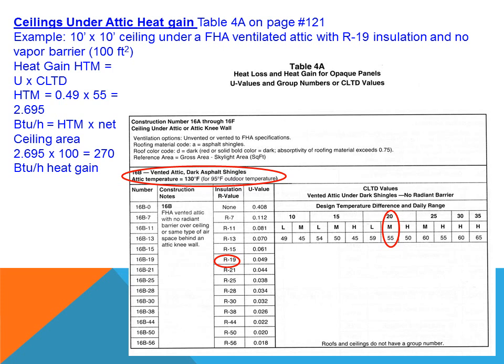Another heat gain we need to consider is the heat picked up through ceilings, because ceilings above an attic can gain a great deal of heat through the larger temperature difference. The attic may be many degrees higher — for example, 130 degrees compared to an outdoor ambient of only 95 degrees. Because of that, we need to look at the ceiling transfer factor based on the type of insulation in the attic. Without insulation in the attic, we will have to size the heating and cooling equipment drastically larger because of that high temperature difference.